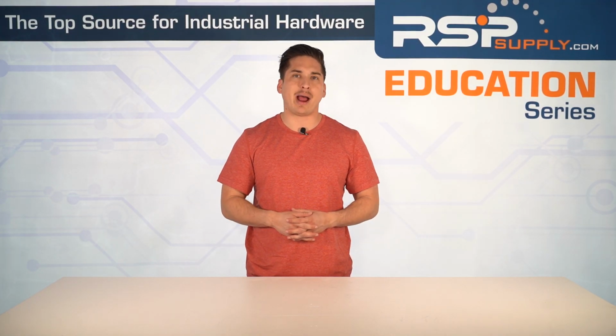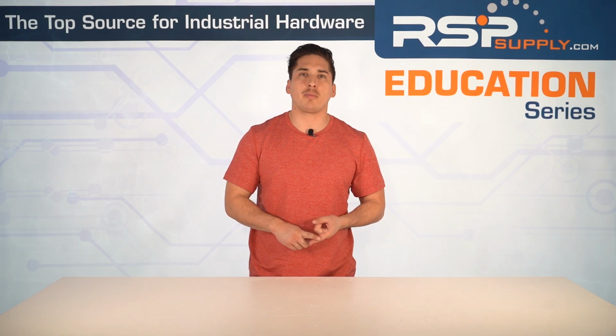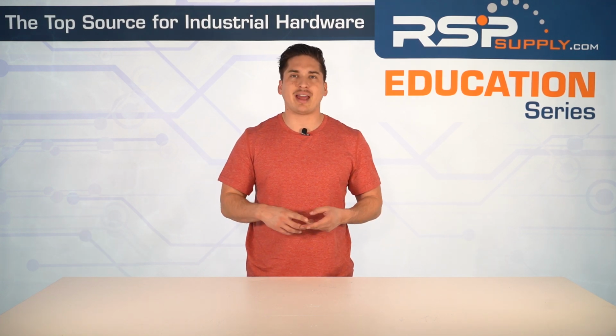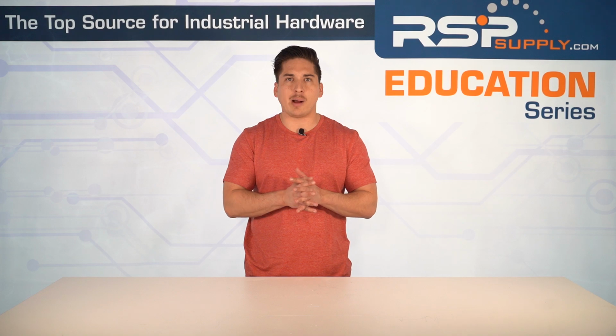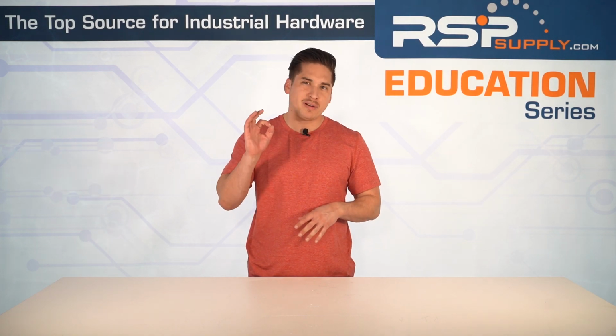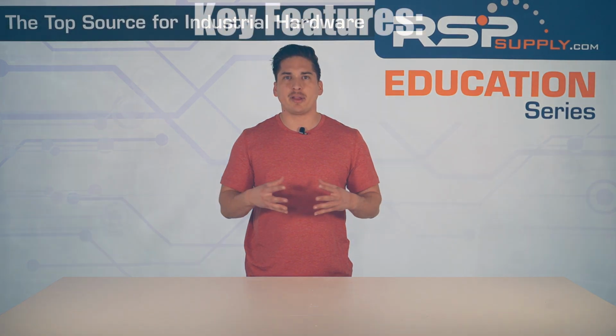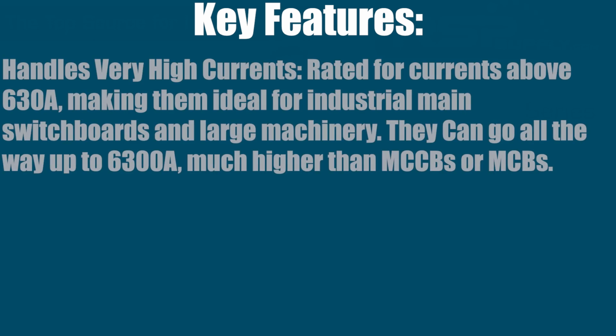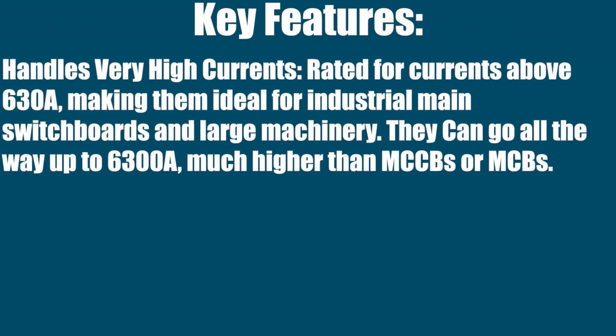So, air circuit breakers are used for heavy-duty protection and power distribution, like large industrial plants and power distribution systems handling high currents, and facilities with complex electrical loads that require precise protection. Let's talk about some of their key features and why they stand out. They handle very high currents. ACBs are rated for currents above 630 amps, making them ideal for industrial mains switchboards and large machinery. They can go all the way up to 6,300 amps, a lot higher than MCCBs or MCBs.